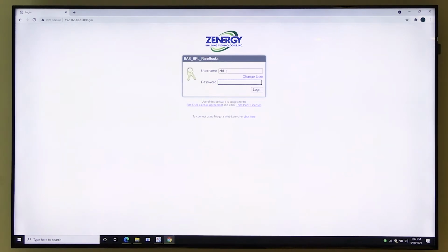It's a communication network. That all goes back to what you're looking at here, which is the web page hosted by that server. So everything you're looking at on this, when I'm clicking through these screens, is basically whatever that server can see. At times, that server might not be able to see anything because the communication is down, or there's a power issue, or ideally everything is communicating and operating correctly. So we're going to go over how you can troubleshoot whether or not what you're looking at is actual live data, because that's important to know, and the steps to troubleshoot that.